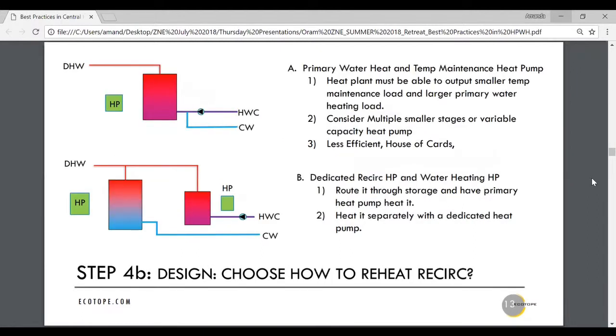Next is choosing how you're going to reheat the recirc system. There are two ways to do it: either you have a primary hot water storage and run your recirc through that, with one heat pump or staged heat pumps managing it, or you simply split off the function—one heat pump system does just the water heating, and a separate one does the temperature maintenance. Our best, most efficient, least troublesome designs are where we split them off: temperature maintenance as one heat plant, and primary water heating as another. They both shine when you do that. That's an area we've been focused on.